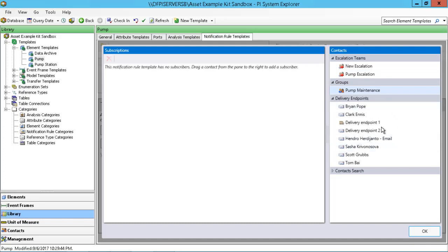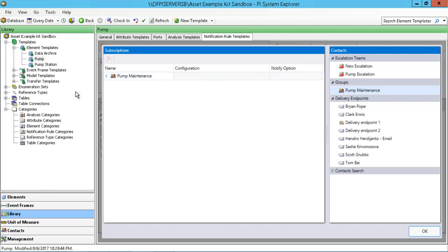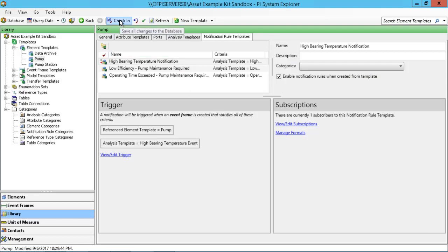We have emails, but you can also create delivery endpoints to web services. Not only could we send a notification to a maintenance worker or someone who needs to know about the health of this asset, we could also potentially start the planned maintenance process by sending information via web services — delivering that to a web services endpoint for the maintenance management system. So not only are you notifying people, you're also notifying systems. I'll drag and drop one of those pre-created groups over into the subscriptions window and click OK. We want to make sure all changes are checked in, and the next time this high bearing temperature notification kicks off, we'll get a message in our inbox with that configured content.